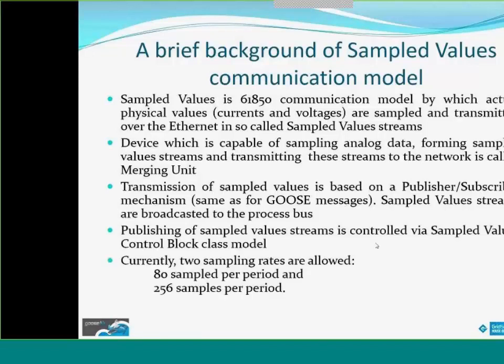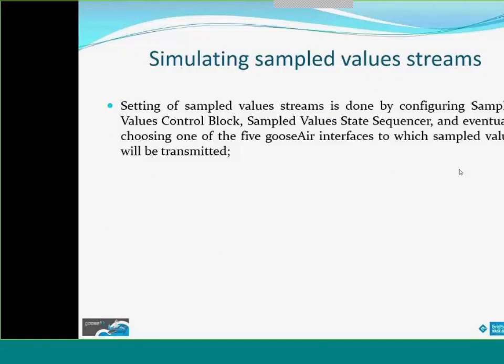So, as for GOOSE messages, I also prepared a brief background on the Sampled Values communication model. If you agree, I could skip these parts too, and start with the simulations. Okay, configuring and transmitting those sample value streams on gooseAir is done very similarly to goose simulations, meaning that firstly the user needs to configure the sample values control block and its parameters, then configure the sample value state sequencer, and eventually choose one of the available gooseAir interfaces to which sample value streams shall be transmitted.